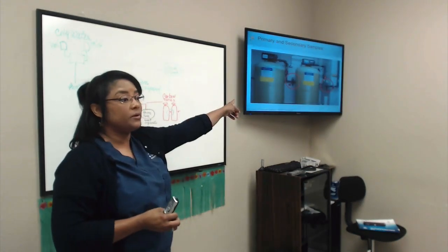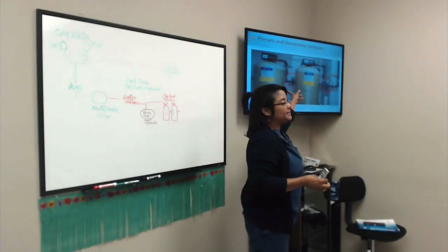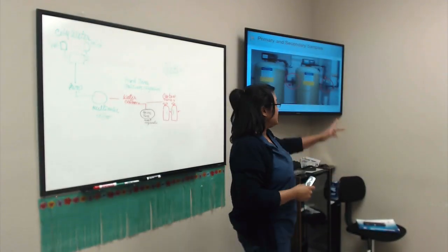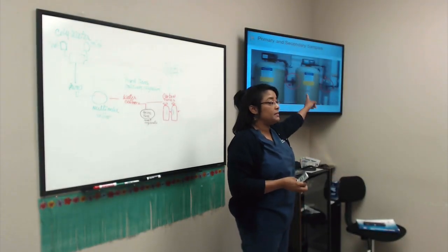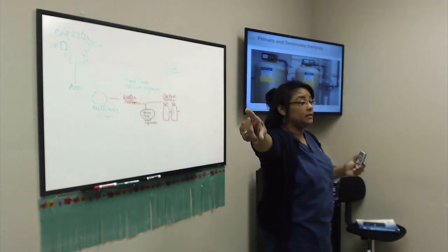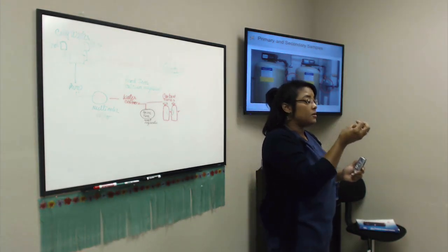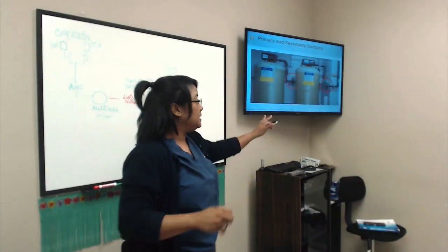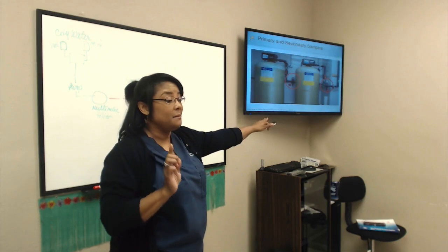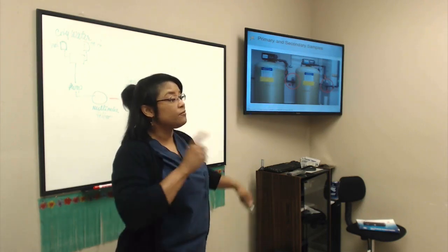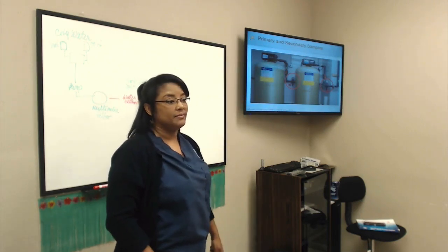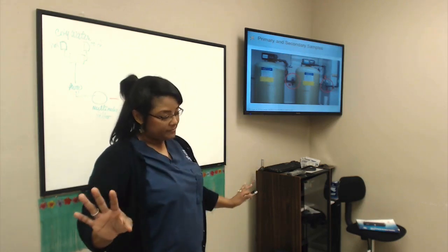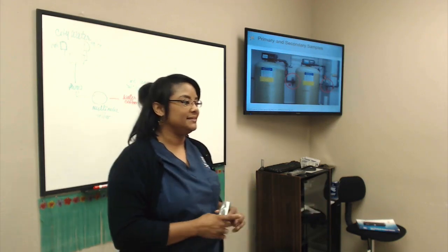This is important. This is not something where you identify it and say, well, I'll tell them later. No. If you identify it, you have to go out immediately and tell the biomed, and if the biomed is not there, tell the nurse in charge, whoever. Somebody has to go in there and test every 30 minutes until this is fixed. The first one is every 4 hours, and this one is every 30 minutes.